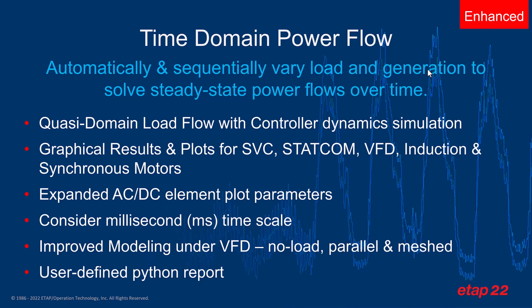So the steady state power flows essentially have a closed loop behavior or closed loop control behavior using the controller dynamics within the simulation. You can also plot the graphical results now for static var compensator, StatComs, VFDs, induction, and synchronous motors. And we've also expanded the AC-DC element plot parameters. One of the other things that you can do in time domain power flow now is consider millisecond timescale instead of purely seconds. And we've also added the ability to include user-defined Python reports.